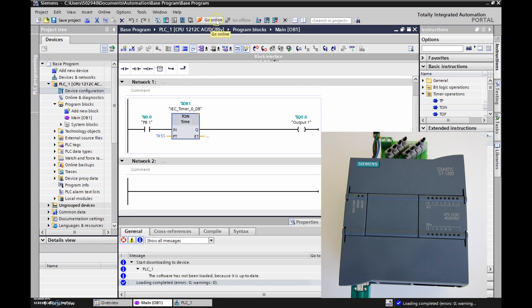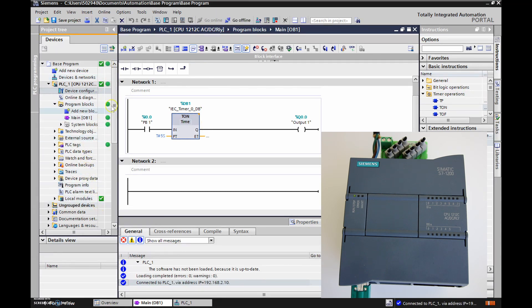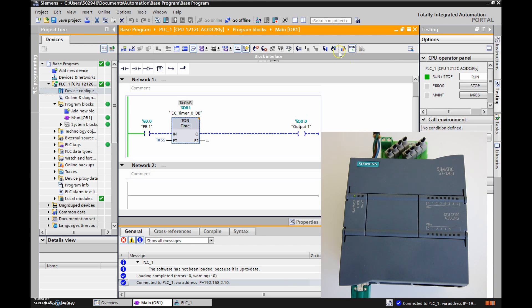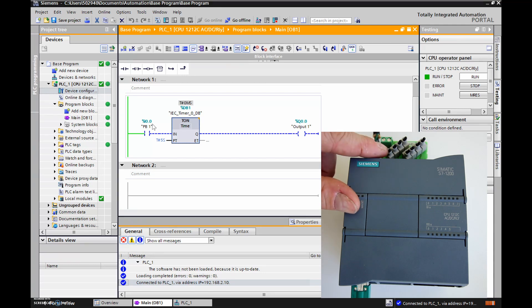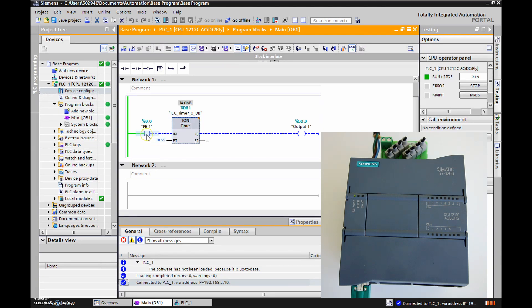Now if I go online it will show check marks all the way across — we are talking to the PLC and the program is now in it. To monitor in real time we turn monitoring on and we'll be able to see the green lines and logic continuity. We have logic continuity to push button number one — Input 0. The DIP switch corresponding to Input 0 is right here; right now it's in the open position, so it's not true. We're looking for an examine-if-closed, so we're waiting for that switch to be closed.